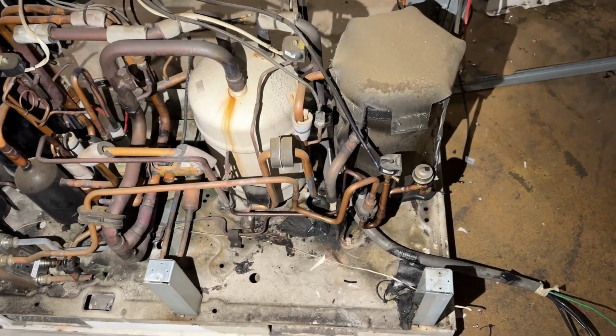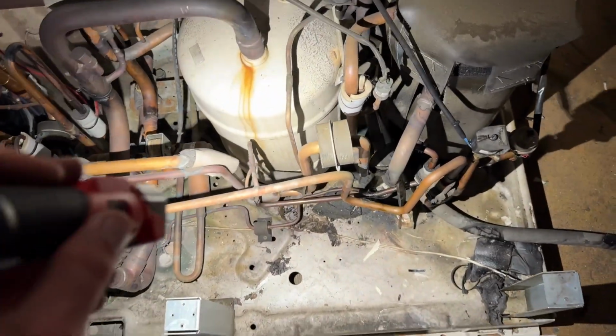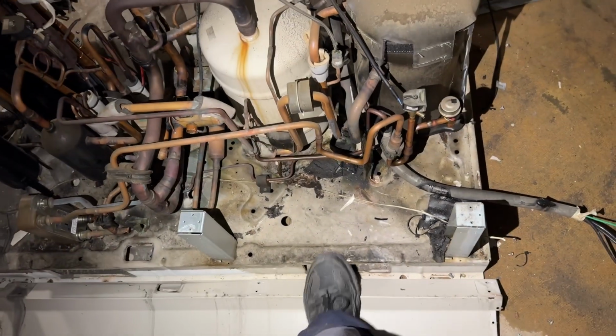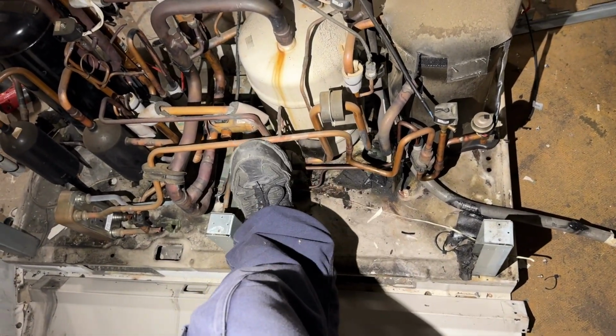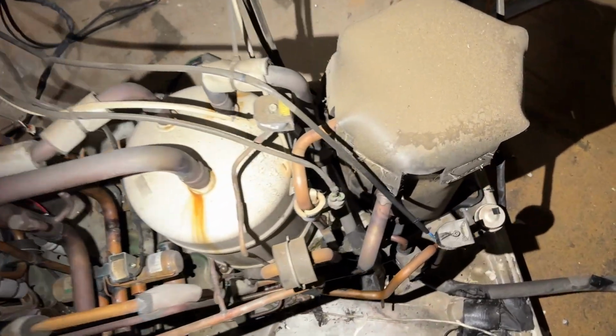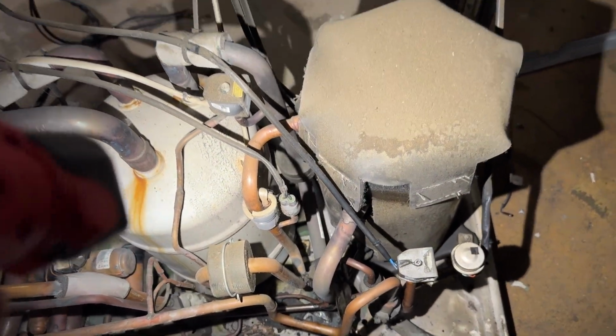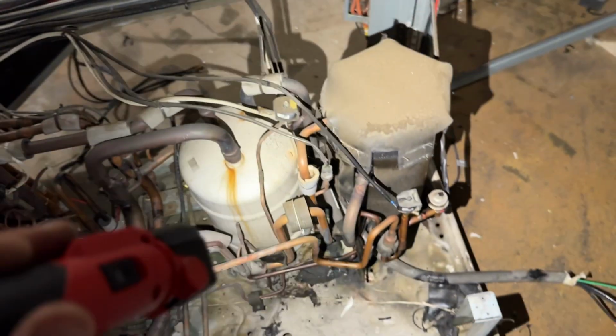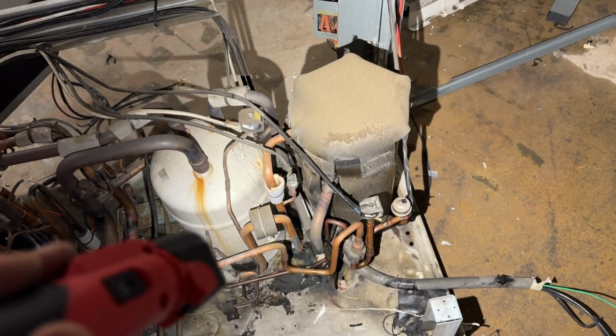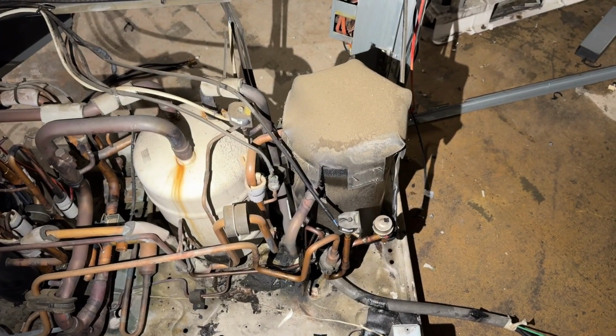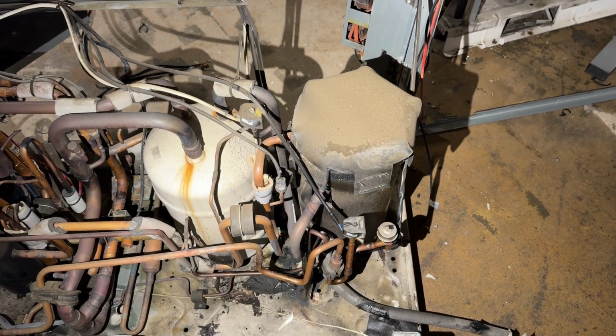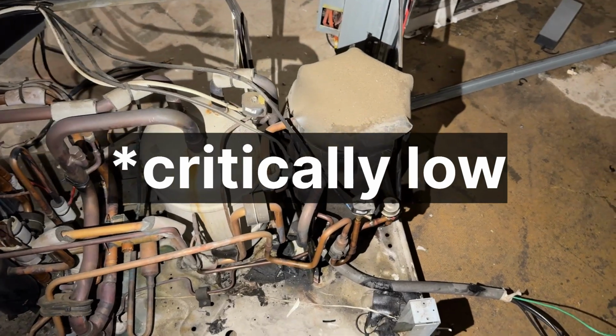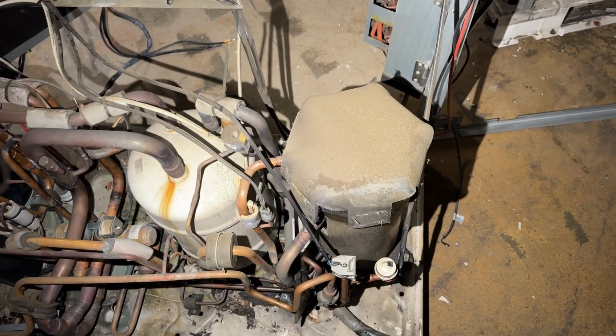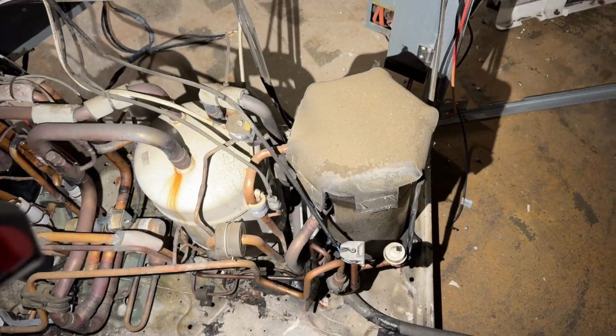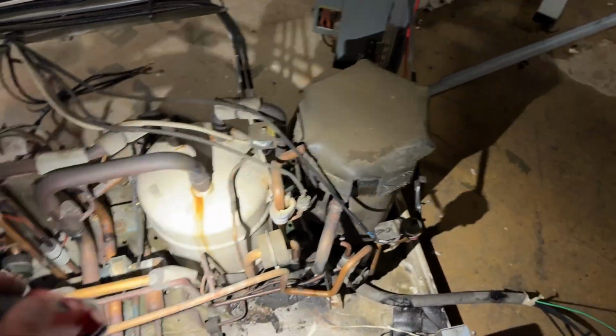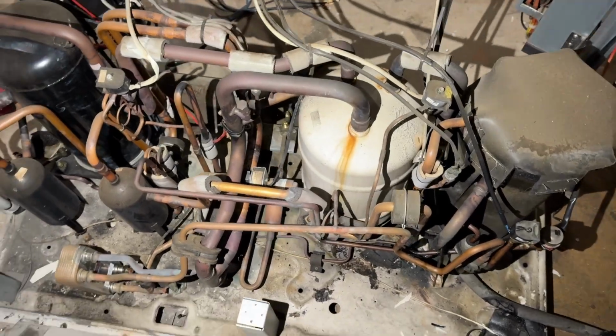Now this is pretty cool too. So the unit is going to take liquid off of this continuous liquid line, take it up here, and it's going to be able to feed it into the compressor. So it can modulate the superheat if it senses that this compressor is not getting enough cooling. And I will say one of the best ways to know that these are low on refrigerant is that you have a real high discharge superheat, because you just don't have the cooling that you need even if this thing is in operation, because you're really struggling with not having enough liquid.